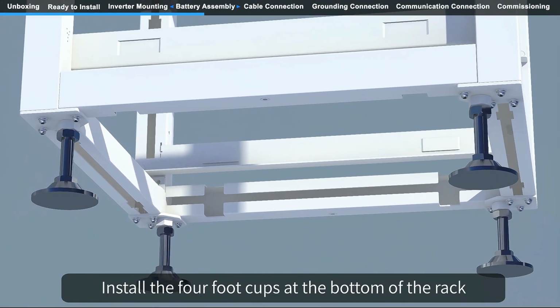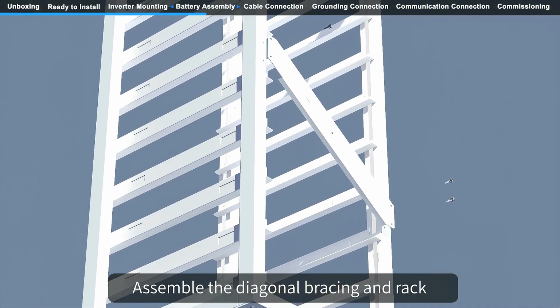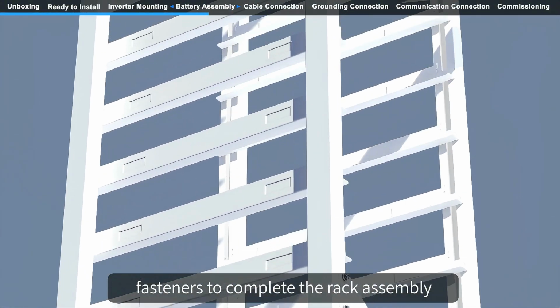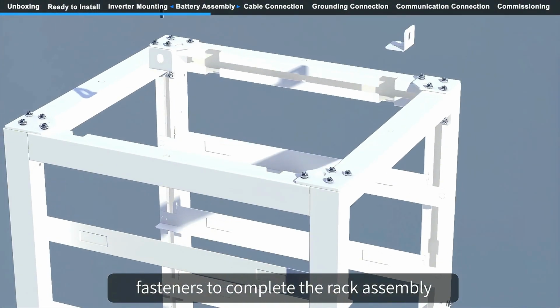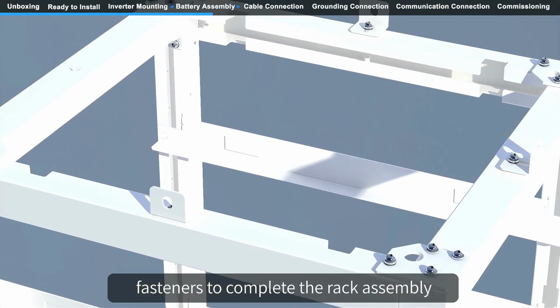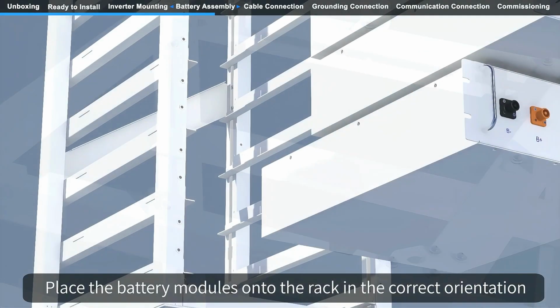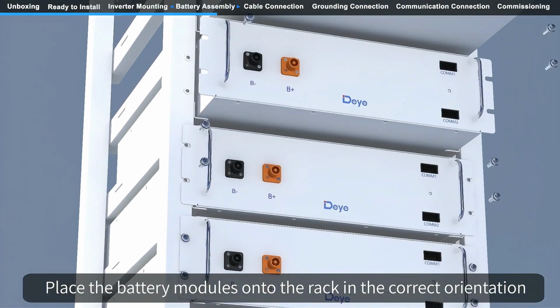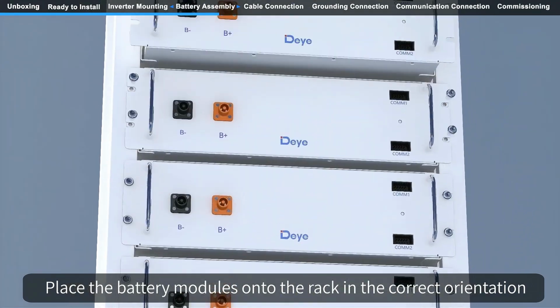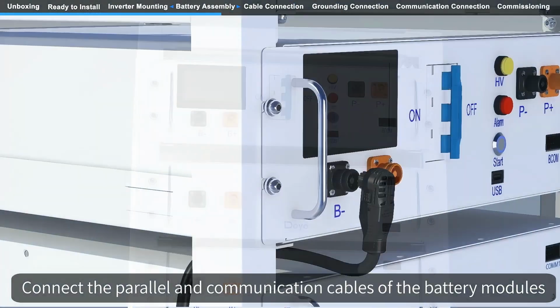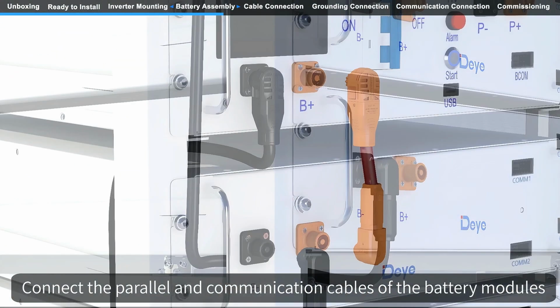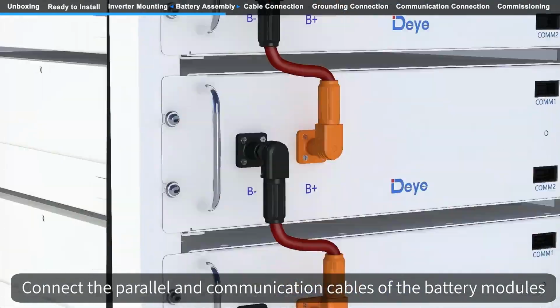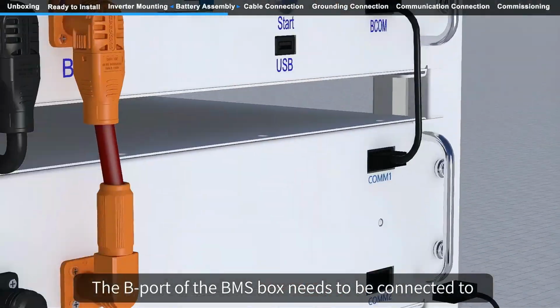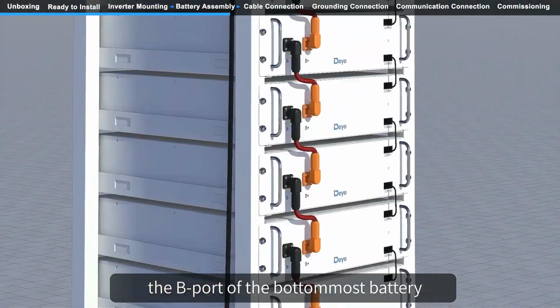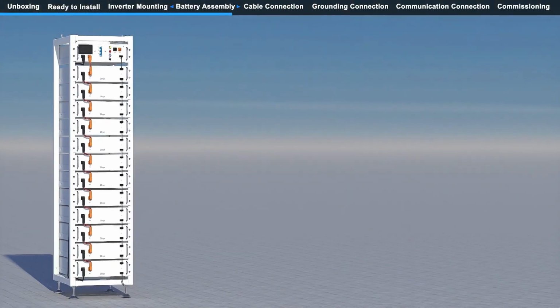Install the four foot cups at the bottom of the rack. Assemble the diagonal bracing and rack fasteners to complete the rack assembly. Place the battery modules onto the rack in the correct orientation. Connect the parallel and communication cables of the battery modules. The B port of the BMS box needs to be connected to the B port of the bottommost battery.